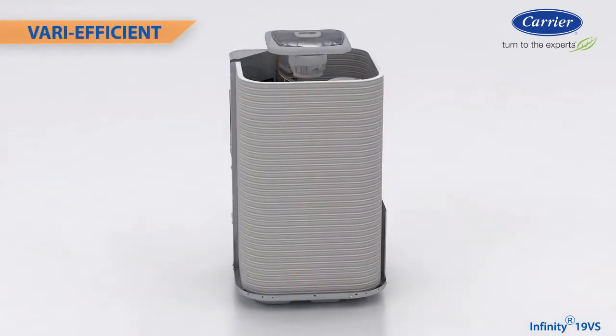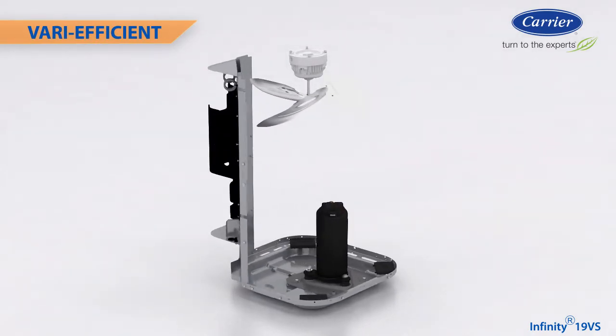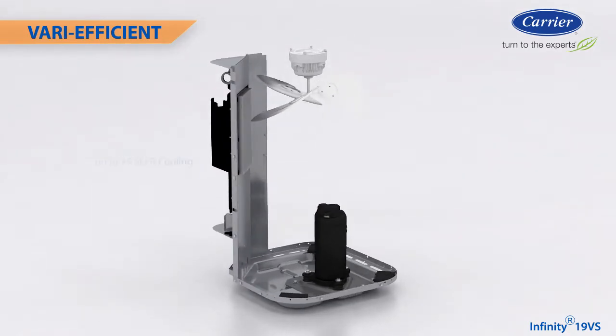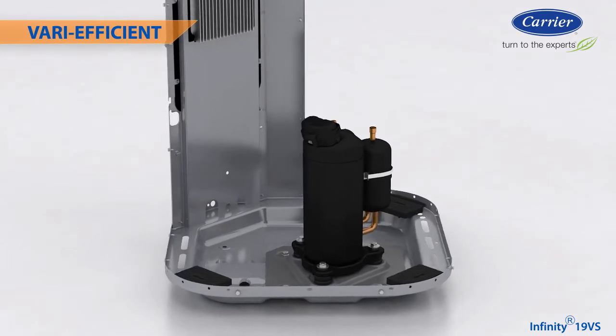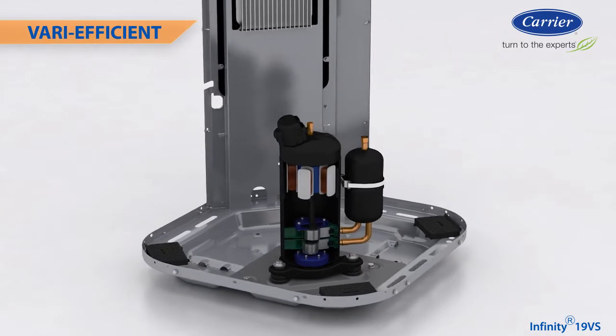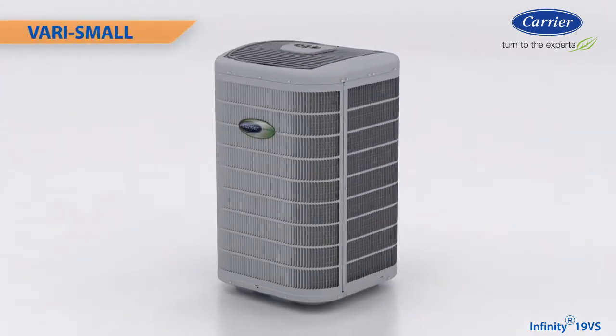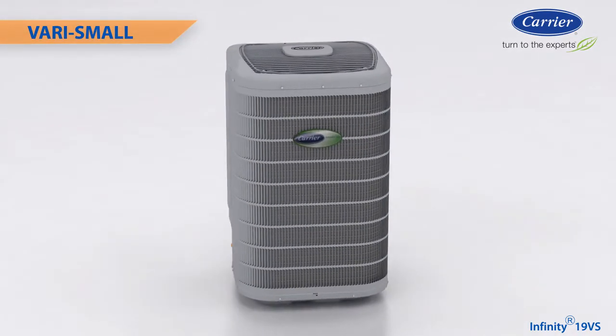Taking a look at the technology behind the performance, the Infinity 19VS includes a new rotary compressor, a new compact ECM fan motor, and a new inverter control — the keys to achieving up to 19 SEER cooling efficiency. This new compressor allows up to 75% capacity reduction, and this type of compressor has a proven record of performance and reliability in millions of systems globally. The Infinity 19VS is the smallest ducted air conditioner on the market with a variable speed compressor.